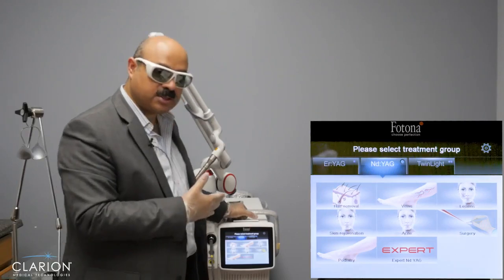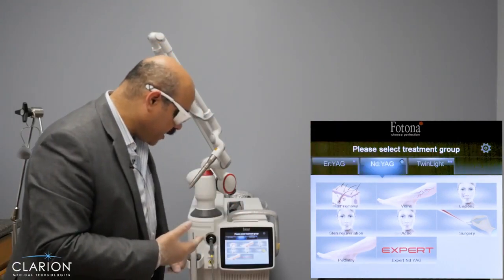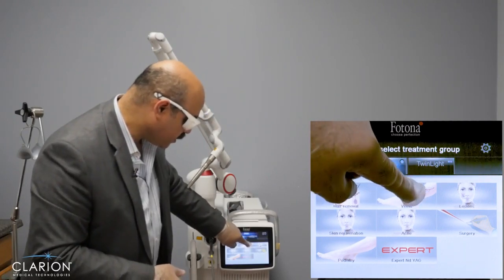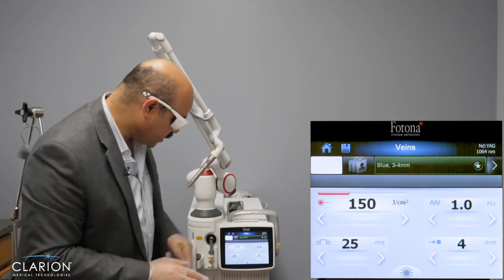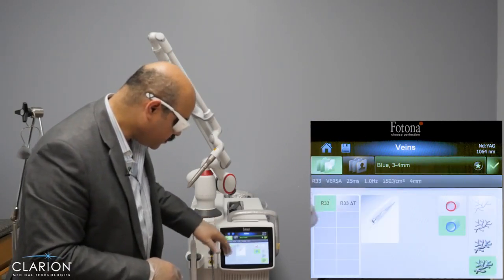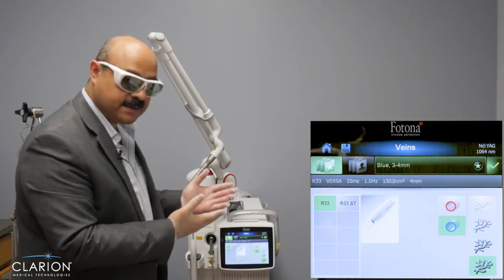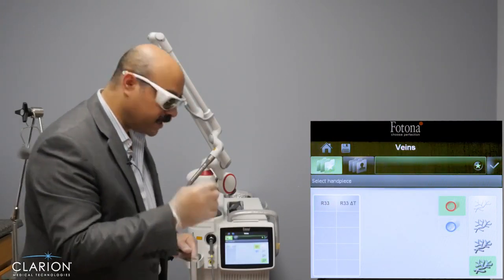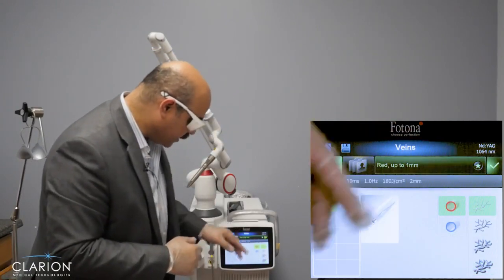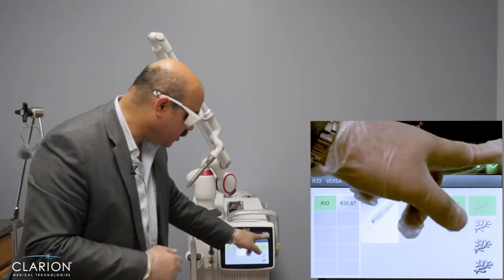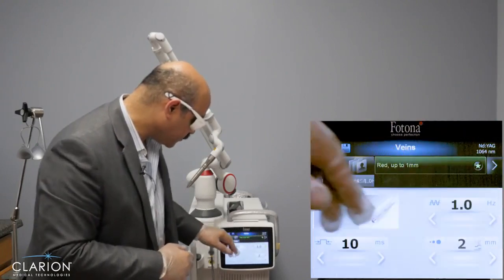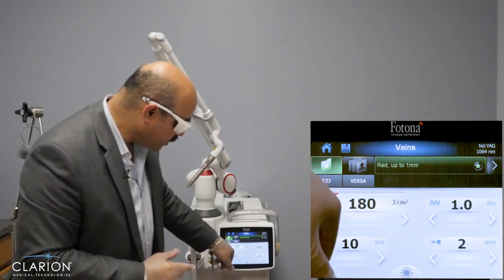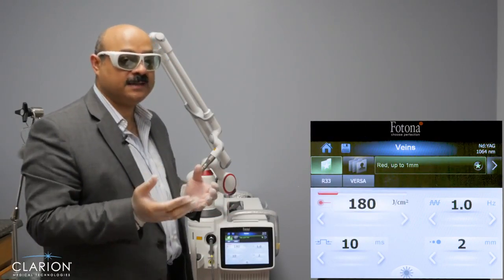On the machine we select the Nd:YAG, and among the treatment options on the SP Dynamis we press 'veins.' Under veins, we select between blue or red — in this case the facial telangiectasia are red, so we press red. Then we determine the size of the vessels; these are very fine vessels so we use the R33 handpiece. We confirm with a check mark and the presets display: two millimeter spot, 10 millisecond pulse duration, and 180 joules.